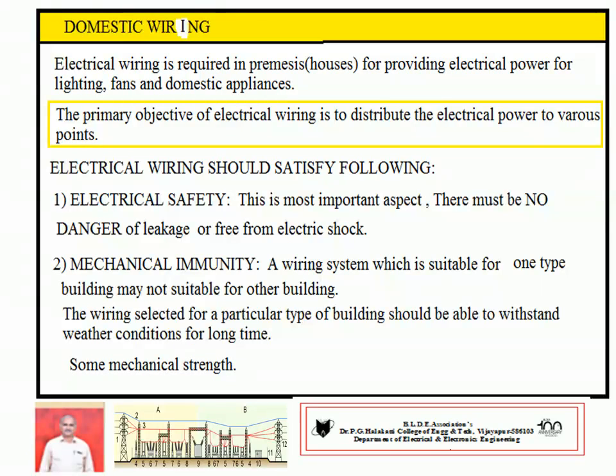Second one, mechanical immunity. A wiring system should be different for different types of buildings. It may depend upon the structure, and upon other environmental conditions and weather conditions. Hence, depending upon the situation, the type of wiring should be selected. As per weather situations, the mechanical immunity should be satisfactory, because wiring should be done for a longer life. It should have a longer life.